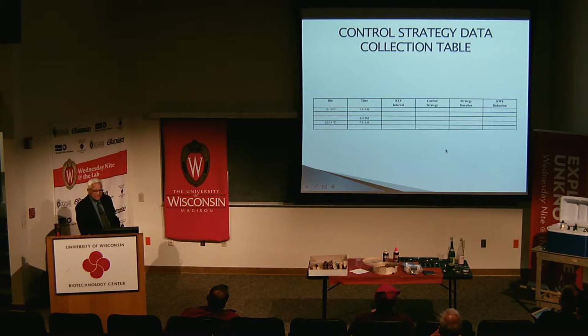Now, the data that you have collected can be represented in this fashion. You can set up for the outdoor air in 3 degrees centigrade bin intervals, or 3 to 5 degrees Fahrenheit, at particular temperature intervals for each of the hours during the 24-hour period, and you select what is the RTP interval. Most of the RTP intervals done in this country are 1 hour. But there is a possibility that will go to as low as 15 minutes to closely match generation with demand.